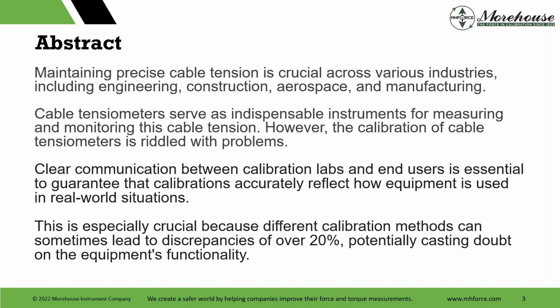There are other methods, guy wires. You can clamp and put a dynamometer in line on an electric line, and there are other things. But cable tensiometers are so much easier than most current methods. And what we find is the actual calibration of these things is just riddled with problems. The real solution is either to set a standard practice in place and tell everybody what you're doing, or better yet, have the contract review with your customer, see how they're using it so you can replicate it. It's especially crucial because different calibration methods can sometimes lead to discrepancies of over 20%, potentially casting doubt on the equipment's functionality. And we're going to go over all of that today.